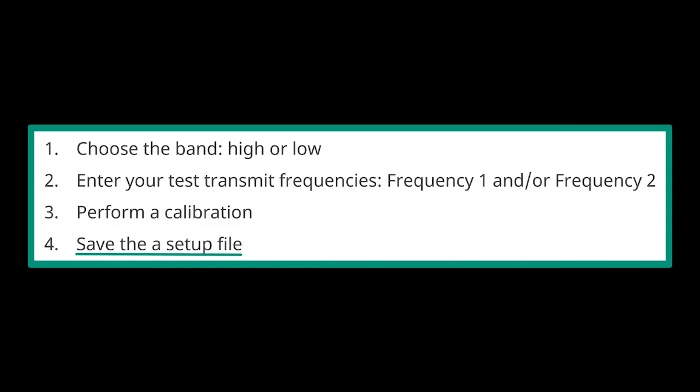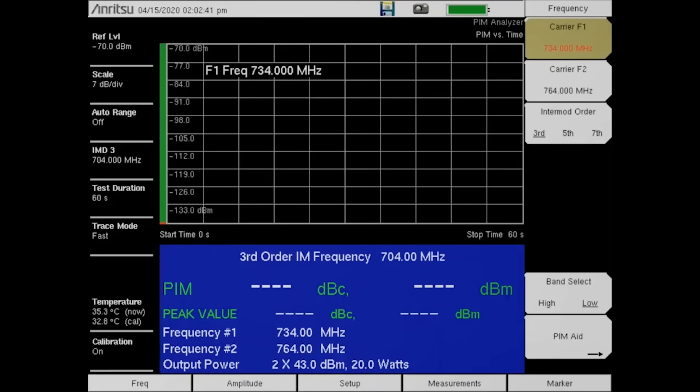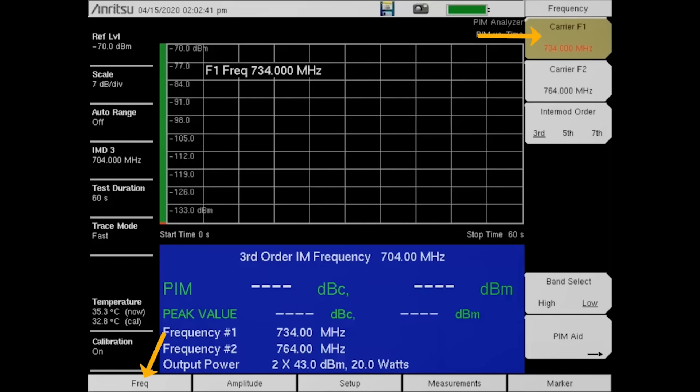Let's go through the process. We will start by entering a custom frequency for frequency one of 733 megahertz. Press the Freq button followed by the Carrier F1 button.